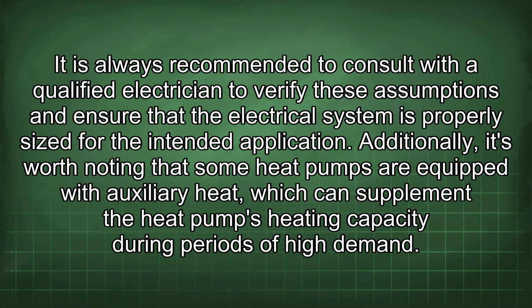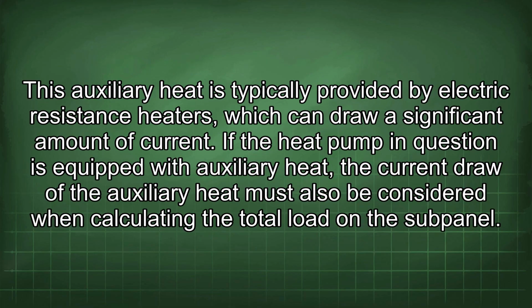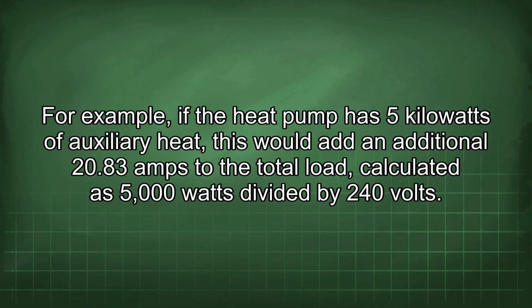Additionally, it's worth noting that some heat pumps are equipped with auxiliary heat, which can supplement the heat pump's heating capacity during periods of high demand. This auxiliary heat is typically provided by electric resistance heaters, which can draw a significant amount of current. If the heat pump in question is equipped with auxiliary heat, the current draw of the auxiliary heat must also be considered when calculating the total load in the subpanel. For example, if the heat pump has 5 kilowatts of auxiliary heat, this would add an additional 20.83 amps to the total load, calculated as 5,000 watts divided by 240 volts.